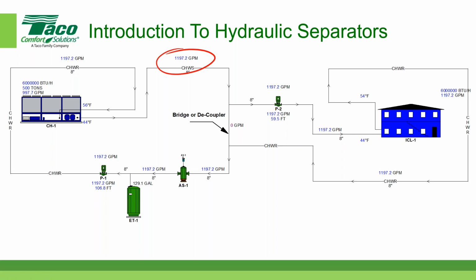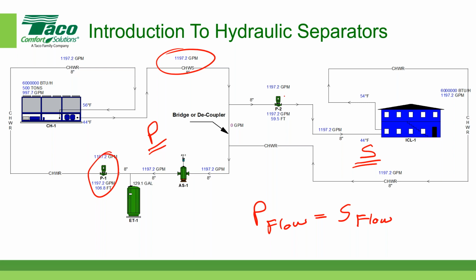And let's say that the primary circuit, again, this is the primary circuit on the left, and this is the secondary circuit on the right. And let's look at a couple of different cases. Let's look at the flow for the primary circuit. Let's say the primary circuit flow is equal to the secondary circuit flow. I'll just make a little note down here. So in other words, I've got my primary pump that's pumping about 1,200 gallons per minute, and my secondary pump is pumping 1,200 gallons.